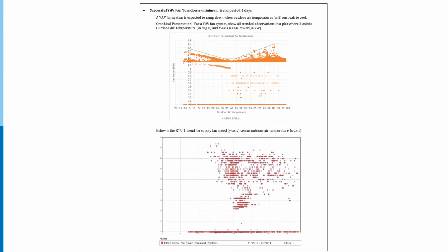So this is a really big one. When we put in a VAV air handling system, we expect it to ramp up and ramp down with the temperature. The top graph that you see on this slide here comes from the engineer's energy model. So if you run the calculations, you run the prediction, that's what the VAV is supposed to look like relative to outside air temperature. That's the predicted behavior. The bottom chart is the actual data. And just in case you can't read the numbers, during the training period, the outside air was between 30 degrees and 75 degrees.